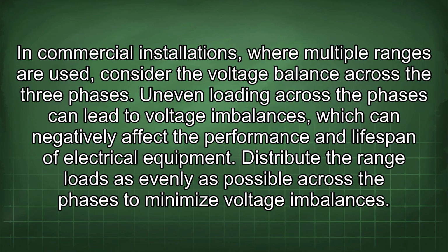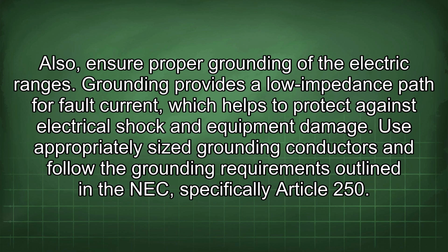In commercial installations where multiple ranges are used, consider the voltage balance across the three phases. Uneven loading across the phases can lead to voltage imbalances, which can negatively affect the performance and lifespan of electrical equipment. Distribute the range loads as evenly as possible across the phases to minimize voltage imbalances. Also, ensure proper grounding of the electric ranges. Grounding provides a low impedance path for fault current, which helps to protect against electrical shock and equipment damage. Use appropriately sized grounding conductors and follow the grounding requirements outlined in the NEC, specifically Article 250.